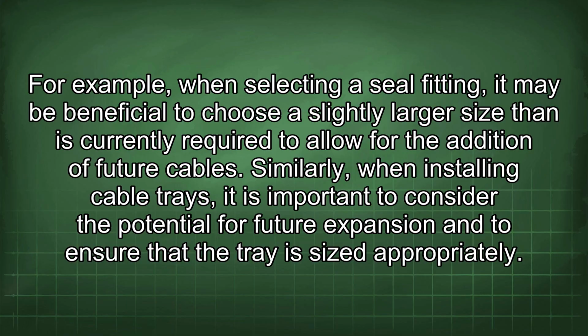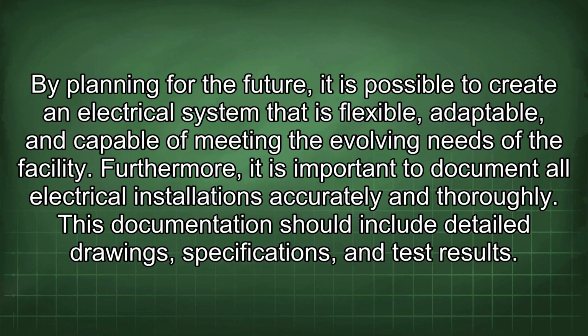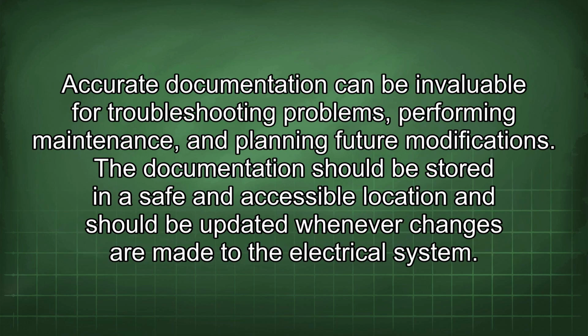Similarly, when installing cable trays, it is important to consider the potential for future expansion and to ensure that the tray is sized appropriately. By planning for the future, it is possible to create an electrical system that is flexible, adaptable, and capable of meeting the evolving needs of the facility. Furthermore, it is important to document all electrical installations accurately and thoroughly. This documentation should include detailed drawings, specifications, and test results. Accurate documentation can be invaluable for troubleshooting problems, performing maintenance, and planning future modifications.